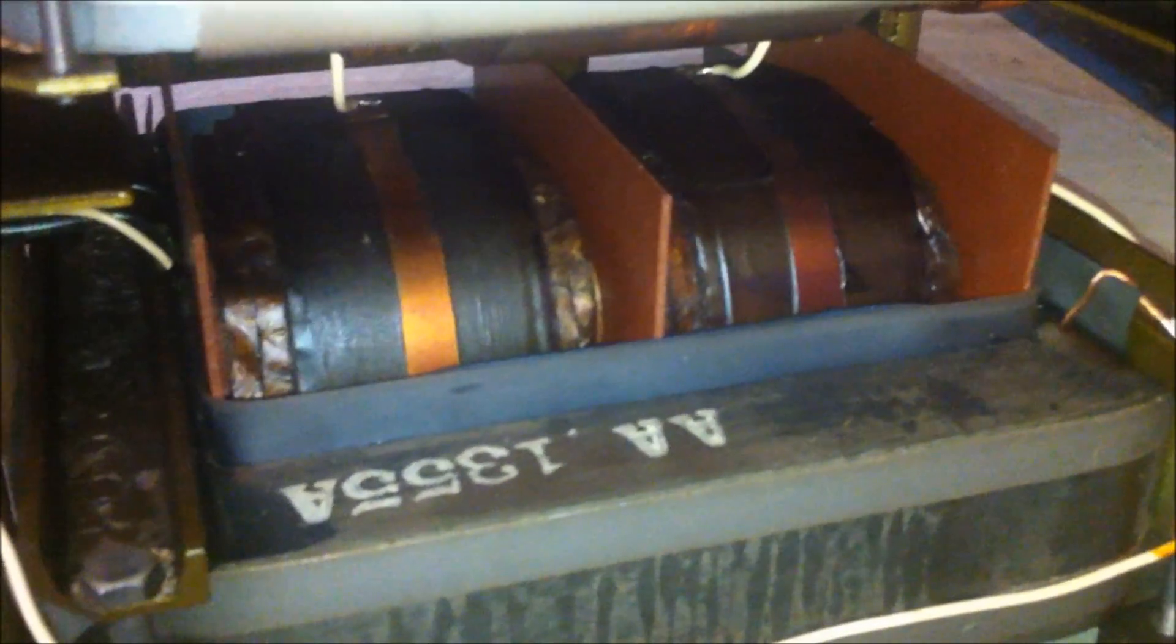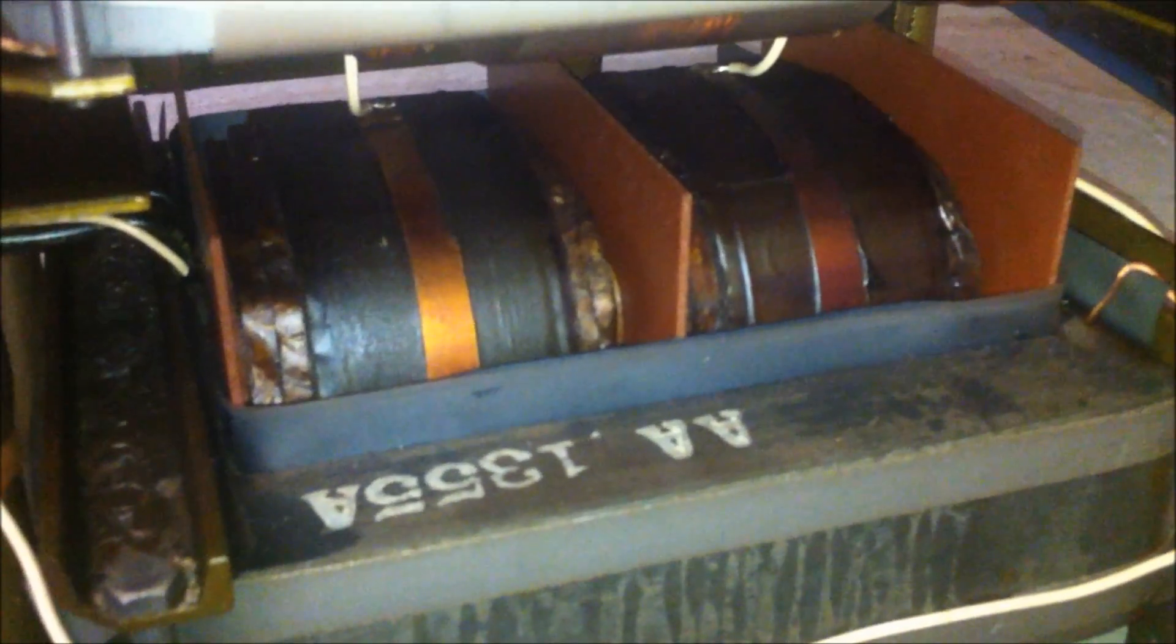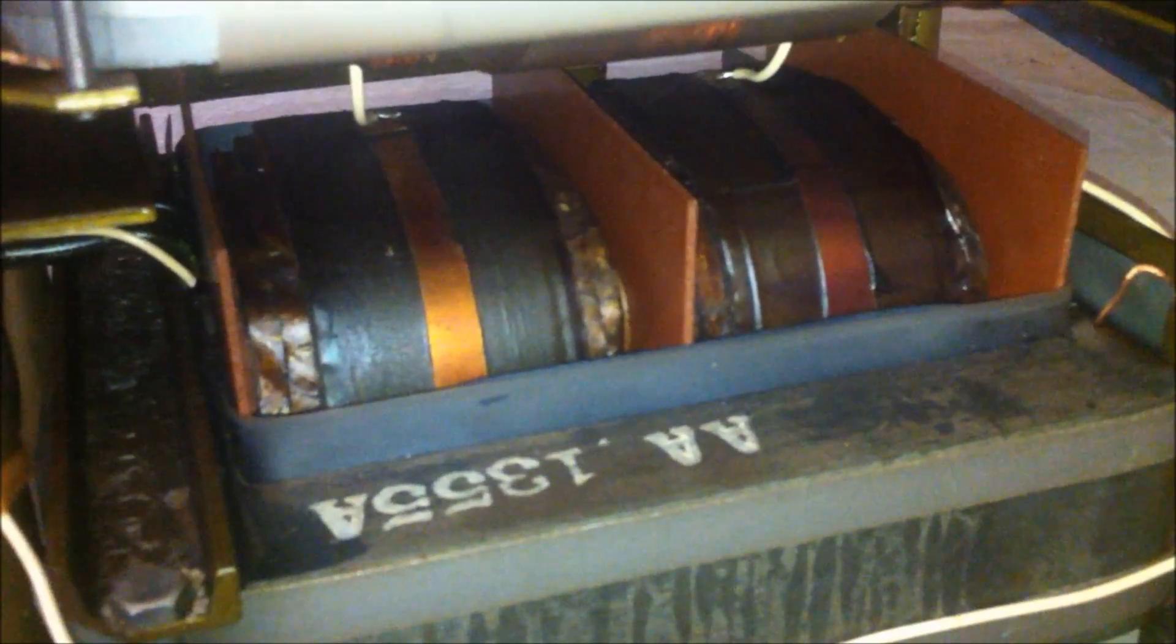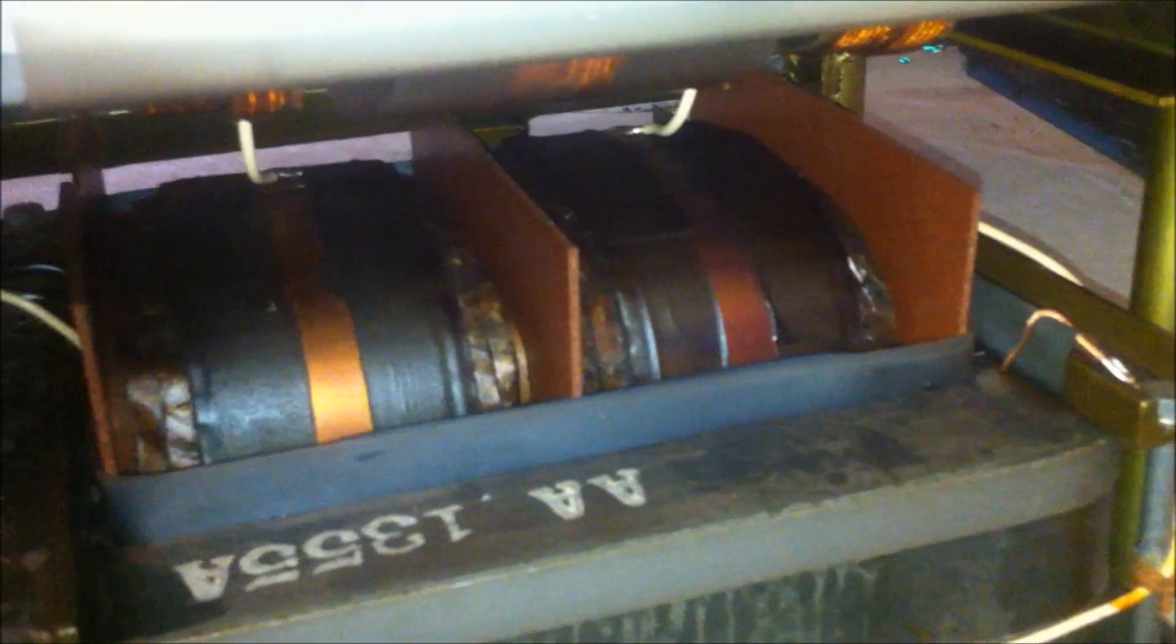which go straight in under here to the level one transformer which is the high voltage step-up transformer. You can see the output wires from the secondaries here that are split in half.